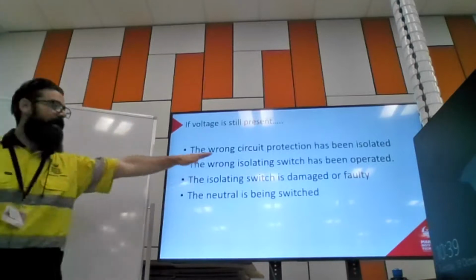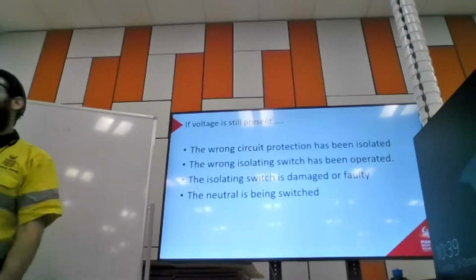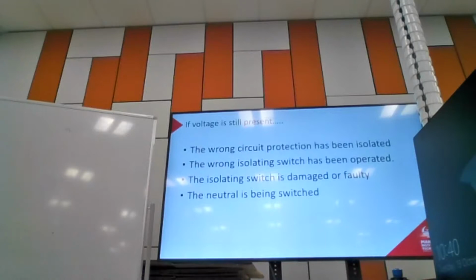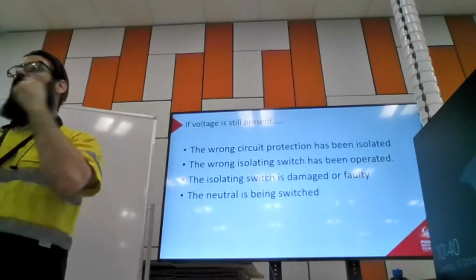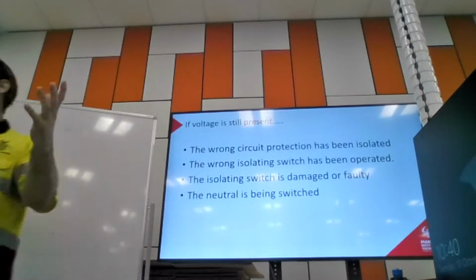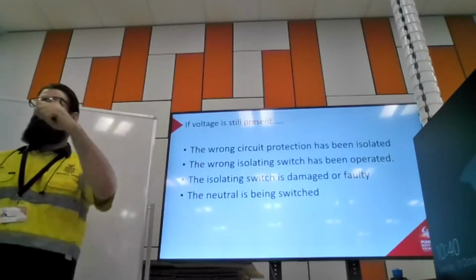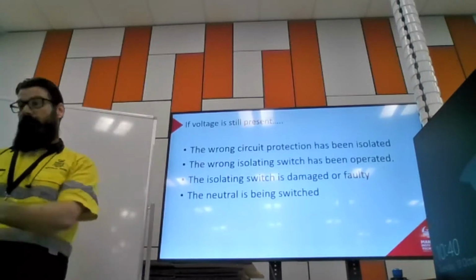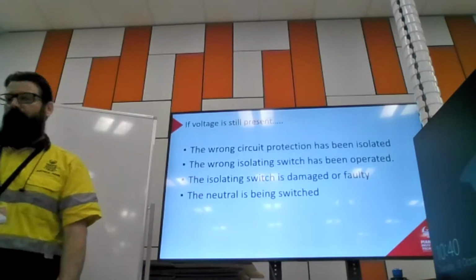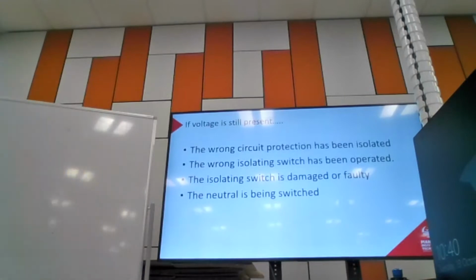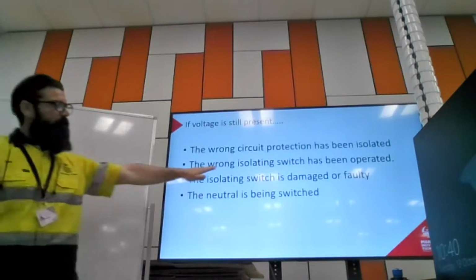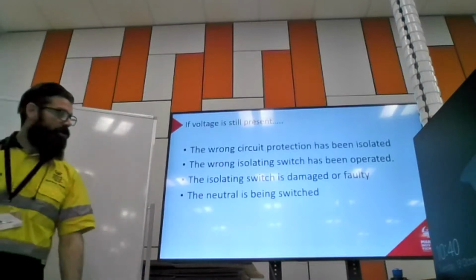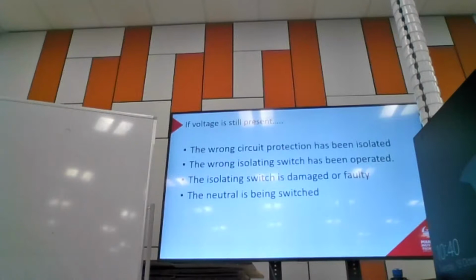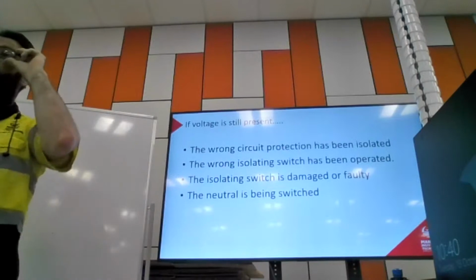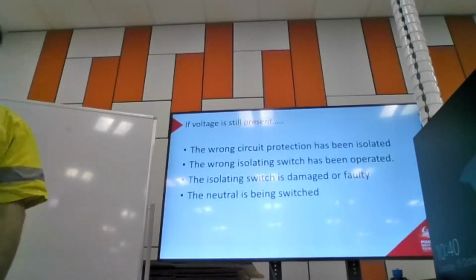So the first thing that we want to look at is whether the wrong circuit protection has been isolated. That's going to be the vast majority of the time. If I isolate it and it's still live, then I've got the wrong one. Especially, of course, if I'm doing trial and error, right? If I'm just flicking them off to see, and I flick one off and I'm still live, then probably I've just isolated the wrong one. Yeah, the same for isolating switches. Might be the wrong isolating switch. The isolating switch is damaged or faulty. So that's possible. It's possible that I could switch something off and it doesn't actually turn off. So that would be something to check.